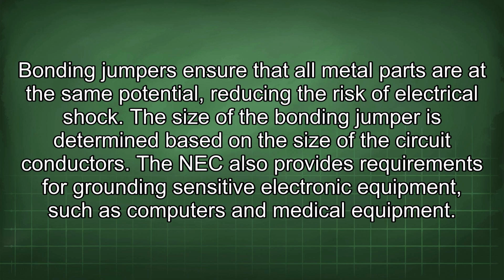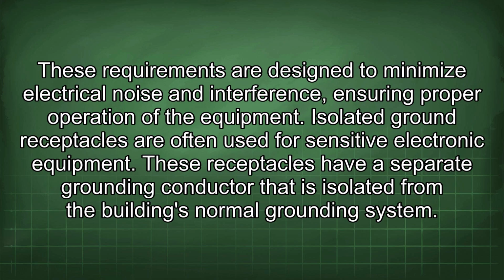The NEC also provides requirements for grounding sensitive electronic equipment, such as computers and medical equipment. These requirements are designed to minimize electrical noise and interference, ensuring proper operation of the equipment. Isolated ground receptacles are often used for sensitive electronic equipment. These receptacles have a separate grounding conductor that is isolated from the building's normal grounding system.